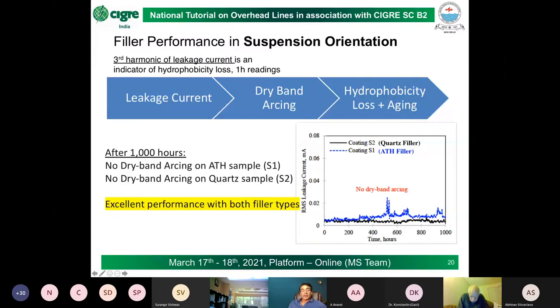What we're looking at is that leakage current causes dry band arcing, which causes hydrophobicity loss, which essentially is aging and pushing the coating to end of life. So this leakage current is a bad idea. It's the enemy of the coating, of silicones, especially in this context.